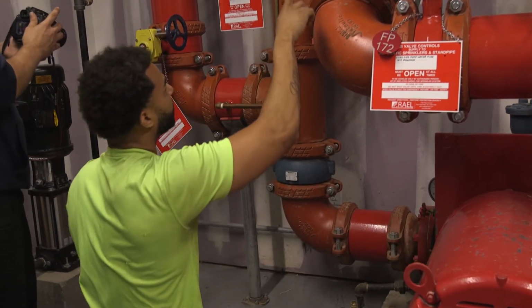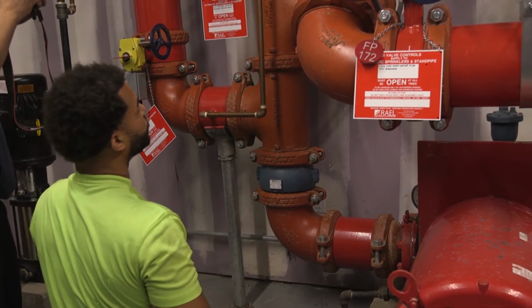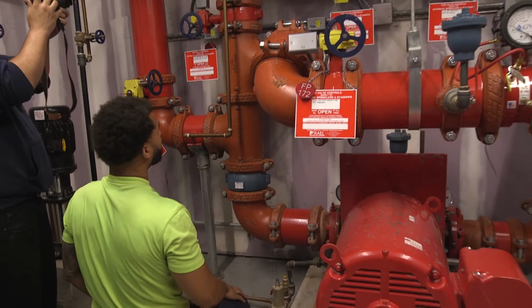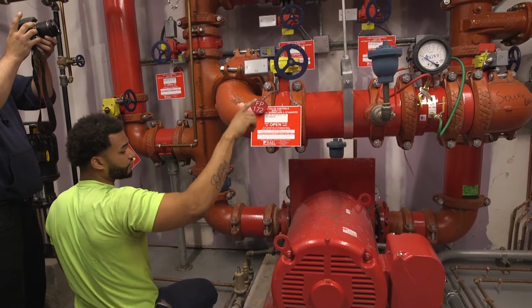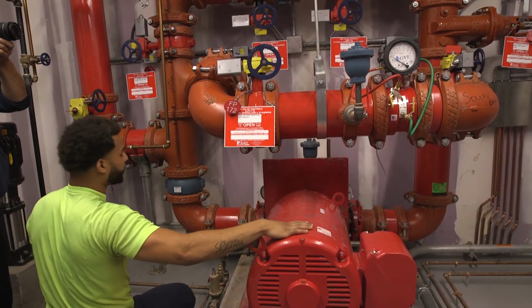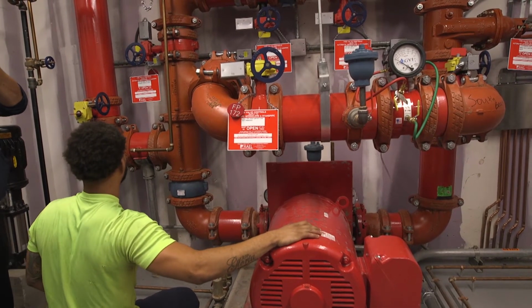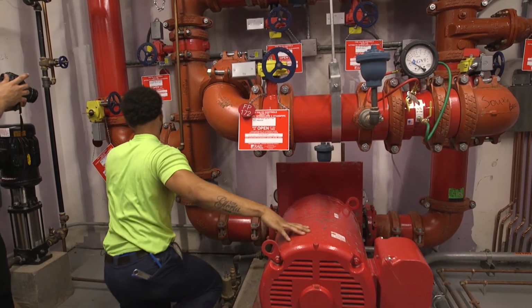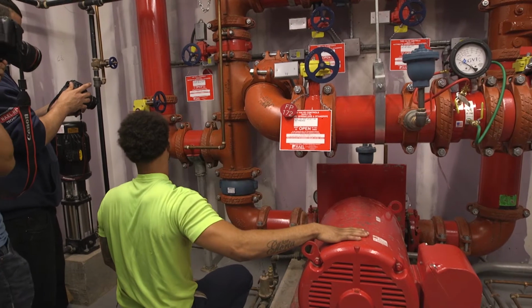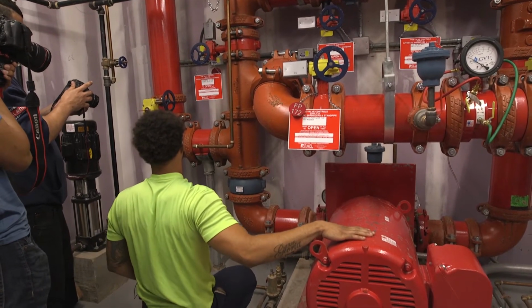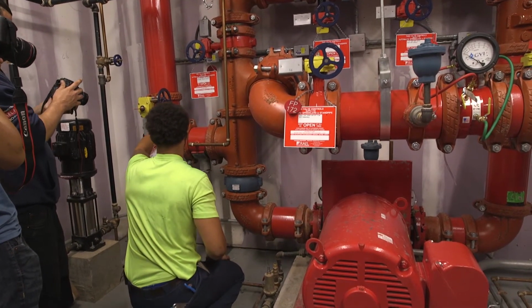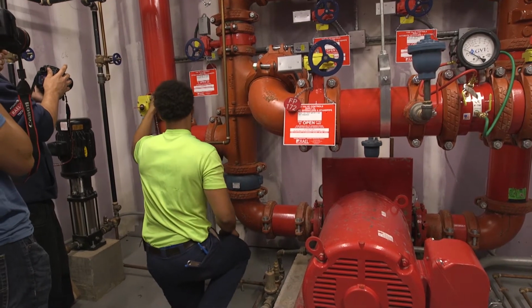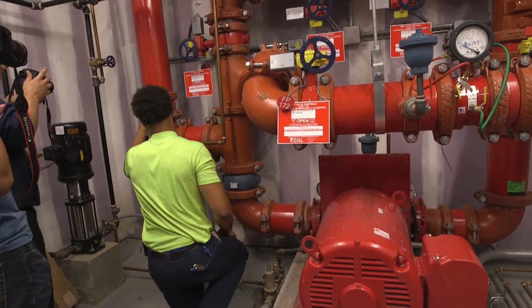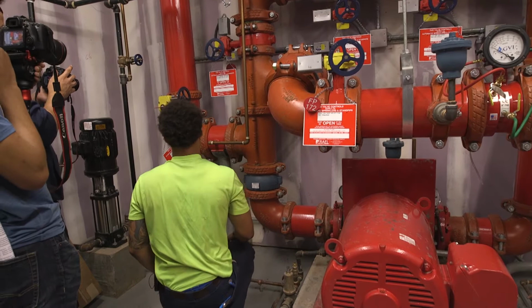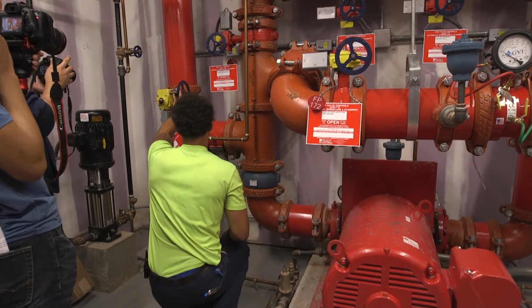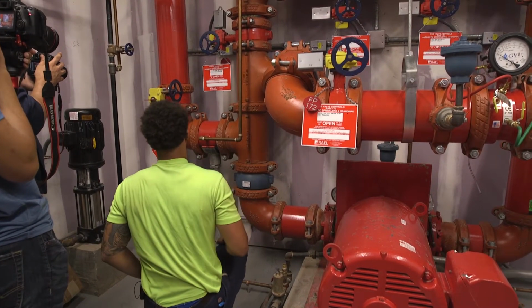So our sensing line is made up of 2 unions, and these unions are pre-drilled with a 3/32 bit to allow water to actually flow into your controller and the controller to actually read system pressure. So this line here is actually what tells your controller what pressure we're reading into the system. So now if we keep going up here, this is an isolation valve, which is a butterfly valve, and it's actually isolating our fire pump test header. This is where tests could be conducted for the fire pump.